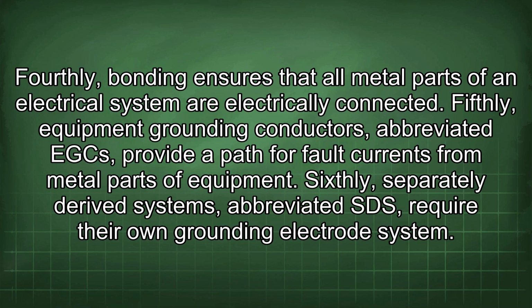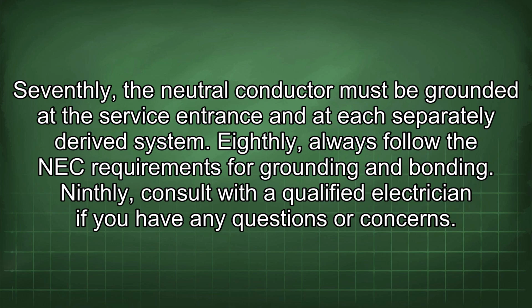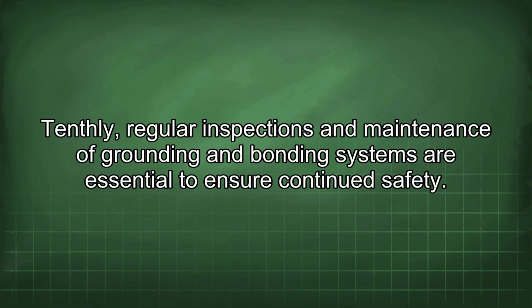Fourthly, bonding ensures that all metal parts of an electrical system are electrically connected. Fifthly, equipment grounding conductors, abbreviated EGC, provide a path for fault currents from metal parts of equipment. Sixthly, separately derived systems, abbreviated SDS, require their own grounding electrode system. Seventhly, the neutral conductor must be grounded at the service entrance and at each separately derived system. Eighthly, always follow the NEC requirements for grounding and bonding. Ninthly, consult with a qualified electrician if you have any questions or concerns. Tenthly, regular inspections and maintenance of grounding and bonding systems are essential to ensure continued safety.